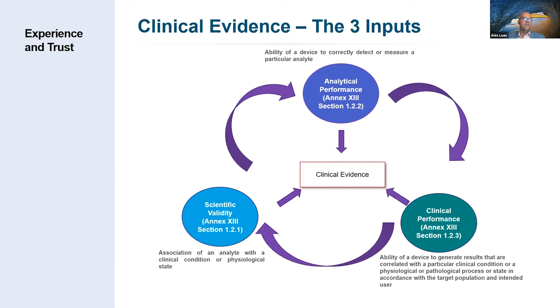Now, talking about clinical evidence and technical documentation, the performance evaluation plan is the document that basically describes your performance evaluation process and how that translates to your device. So your performance evaluation plan may look slightly different for an HIV test as opposed to, for instance, a blood glucose monitoring device, because there are different requirements on state of the art. There's a different intended use, there's different diagnostic practice. Sometimes an assay may give a direct result or an indirect result. Sometimes there may be reference values, sometimes not. So all of these details you can further define in your performance evaluation plan.